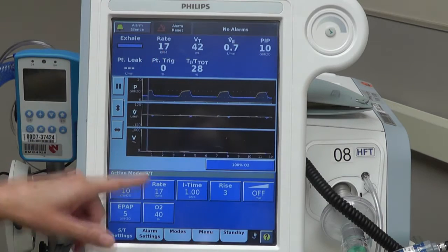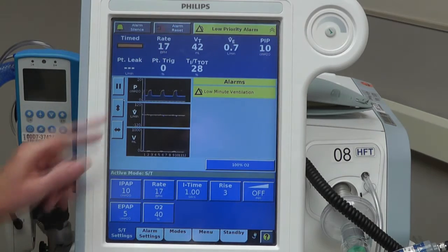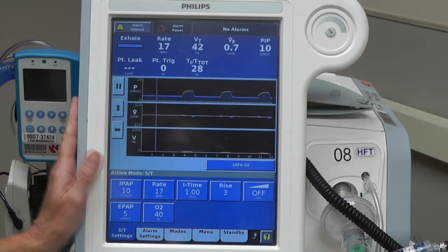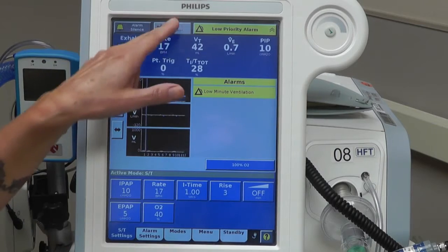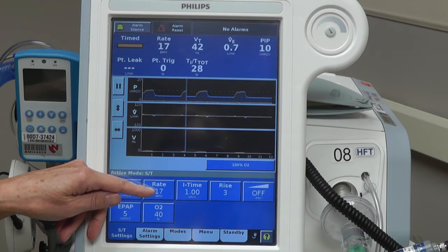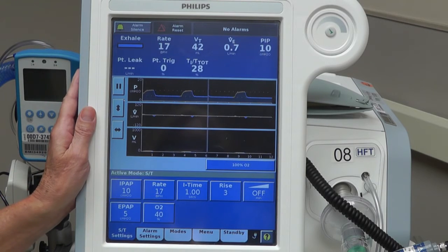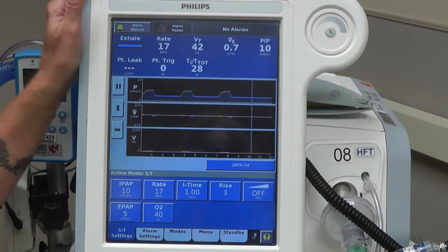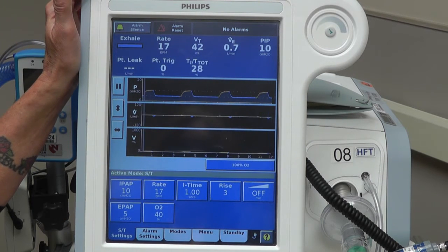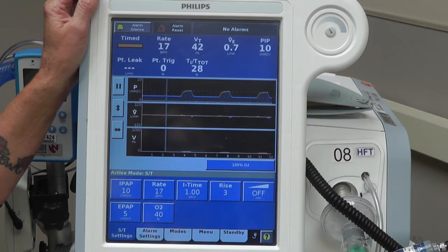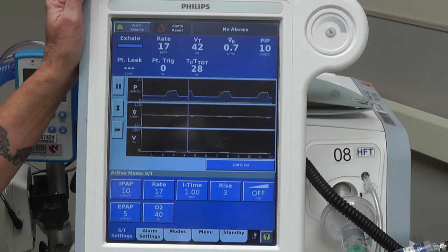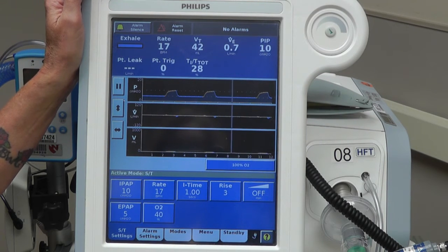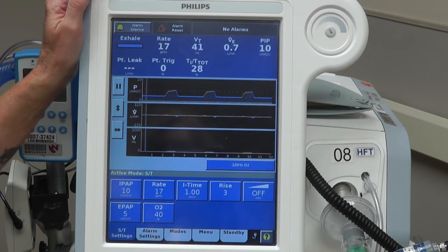The rate that's set is really a backup rate because this is BiPAP, so my patient is breathing on their own spontaneously. So again, this is a backup rate. We usually set the rate at 4 because there is an algorithm in this machine, so if the patient stops breathing for a short period of time, it will kick in a rate. We don't want to set a rate on this patient. We really want them to be breathing on their own and then activate an alarm if they're not breathing.